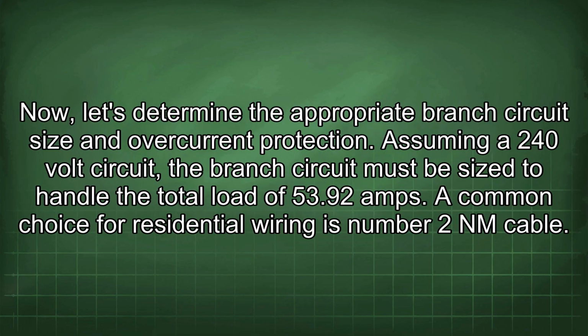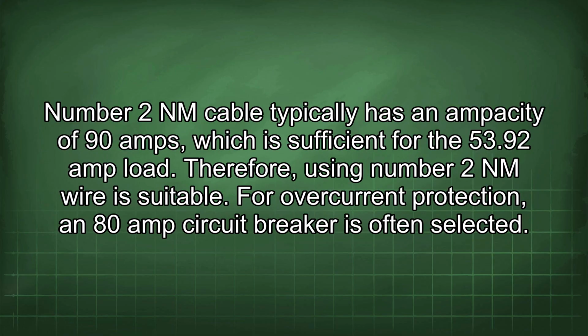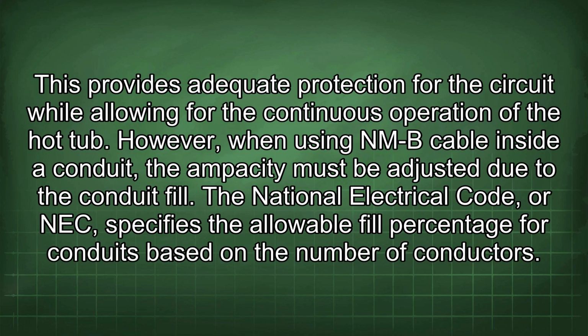Now let's determine the appropriate branch circuit size and overcurrent protection. Assuming a 240 volt circuit, the branch circuit must be sized to handle the total load of 53.92 amps. A common choice for residential wiring is number 2 NM cable. Number 2 NM cable typically has an ampacity of 90 amps, which is sufficient for the 53.92 amp load. Therefore, using number 2 NM wire is suitable. For overcurrent protection, an 80 amp circuit breaker is often selected. This provides adequate protection for the circuit while allowing for the continuous operation of the hot tub.